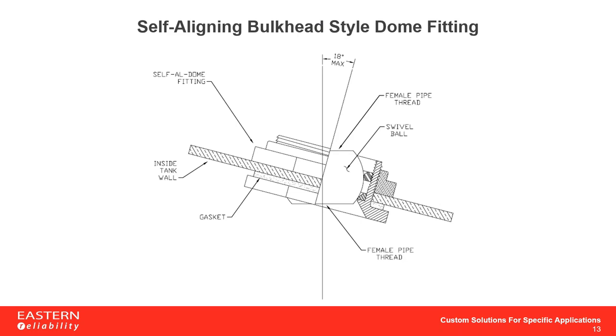Depending on your design and piping layout, you may require a fitting on the dome portion of the tank. These self-aligning dome fittings have a ball swivel incorporated into the design to ensure a nice vertical position for any piping or equipment requiring vertical alignment. They're also useful when an agitator is off-center on the dome, as any vibration or shaft movement won't rub against an open hole in the tank. The fitting also provides extra support to the opening — if wear and tear becomes an issue, you can simply swap out the fitting rather than damaging the tank itself.